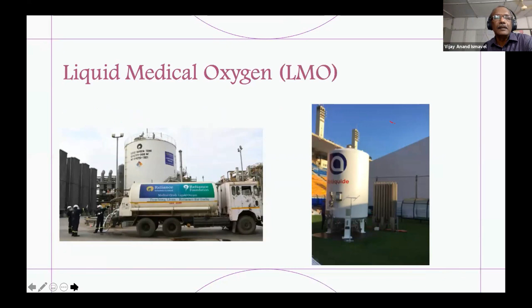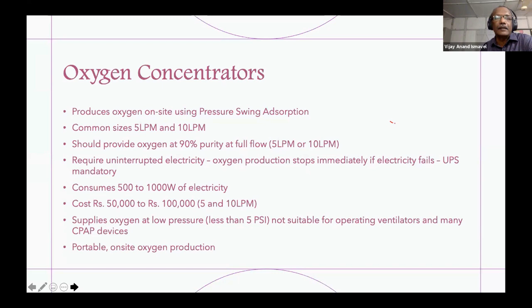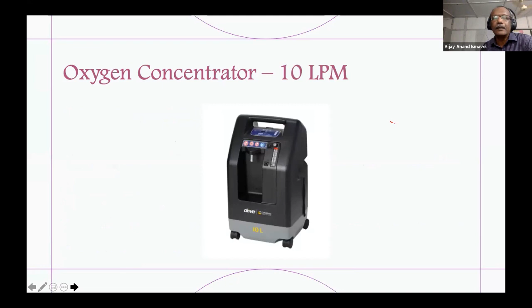So oxygen concentrators use the same principle, except that they are very miniature, portable, commonly available at 5 liters per minute and 10 liters per minute capacity. They should produce oxygen at 90% at full flow. If that is not there, then I think you should not buy that concentrator. So please check that. They also require uninterrupted electricity. The oxygen production stops immediately if electricity fails, and the connected patient will become hypoxic unless you have a UPS. And I've written about the consumption and the costs there. The only problem is it is at low pressure, so it cannot be used to drive ventilators and anesthesia machines and things like that. So that is a standard oxygen concentrator.